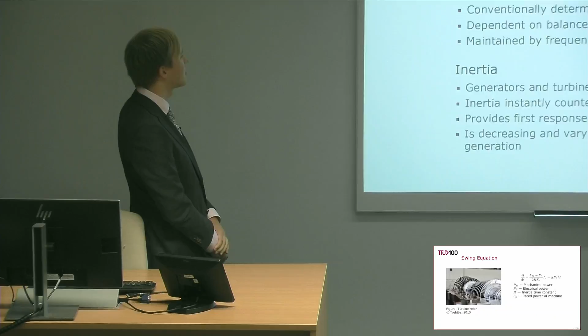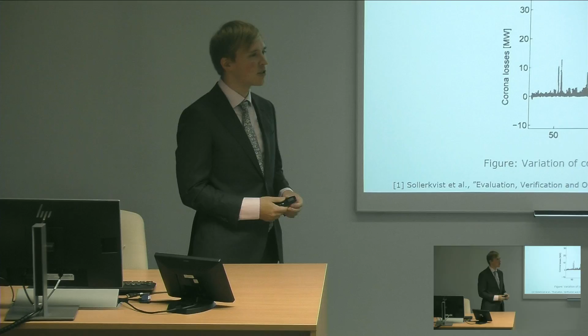Well, as I discussed during the presentation, it is basically caused by systematic measurement errors in the measurement devices, such as current and voltage transformers, as they have certain errors in the measurements. Since we did not have calibrated instrument transformers available, there are some systematic errors in the measurement data. In another experiment I referred to from Sweden, where they did have calibrated instrument transformers, we can still see occasions of corona losses with negative values. So there are, of course, some limits to the accuracy of the measurement data, and this has to be considered.